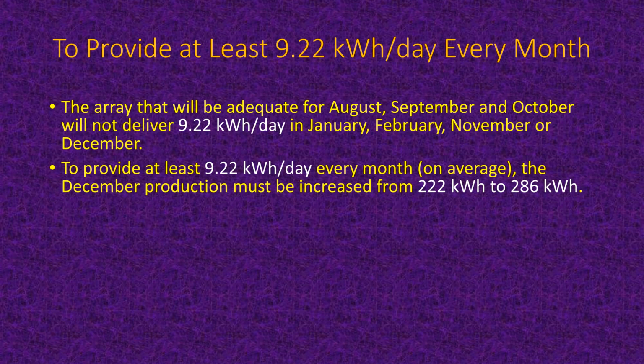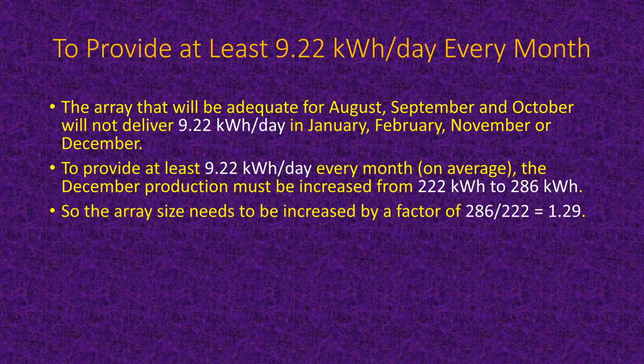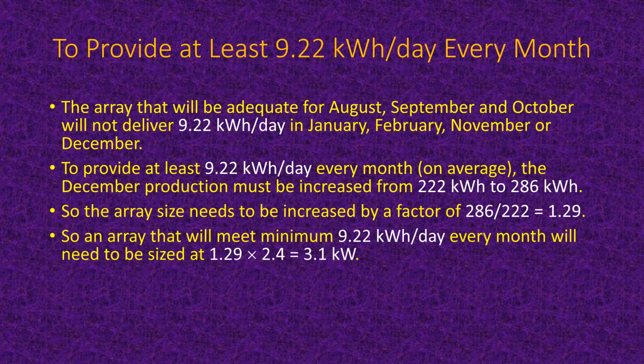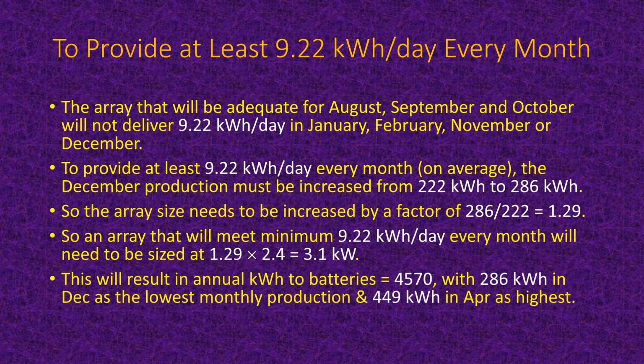So again, 286 over 222 says make it 1.29 times bigger, which now says we should have a 3.1 kW array. Well, 3.1 kW these days is small change. I analyzed 11 systems this morning, and every single one of them was more than 6 kW. Some went as high as 18 kW. So 3.1 is a small array. But that 3.1 kW array is enough to give you those kilowatt hours you need for your backup system every month of the year.